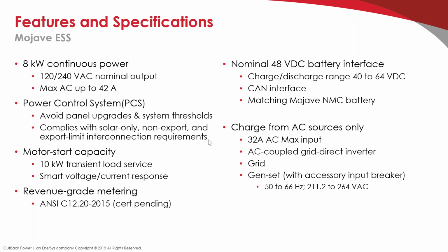Also motor start capacity. We're doing things a little bit differently than we have in the past. We have a 10 kilowatt transient load service. What we actually do with that is, when there's a big load, like a compressor in a refrigerator or a motor in a pump, typically what they need is a lot of current.